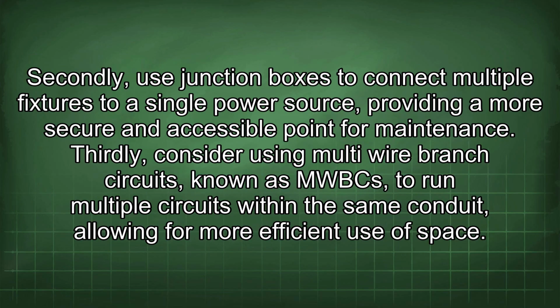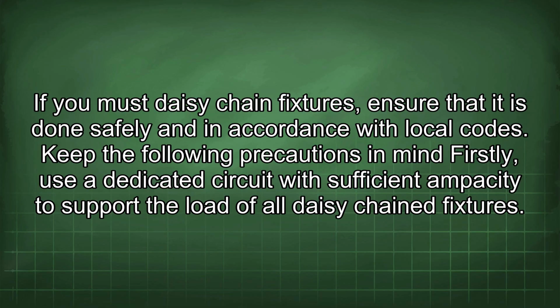Secondly, use junction boxes to connect multiple fixtures to a single power source, providing a more secure and accessible point for maintenance. Thirdly, consider using multi-wire branch circuits, known as MWBCs, to run multiple circuits within the same conduit, allowing for more efficient use of space. If you must daisy chain fixtures, ensure that it is done safely and in accordance with local codes. Keep the following precautions in mind.